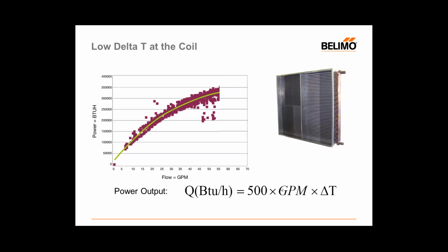This heat exchange process is governed by this formula, and most people in this industry are fairly comfortable or familiar with this formula, which is that the power output in BTUH is defined by 500 times the flow rate in GPM times the delta T in degrees Fahrenheit. So to really understand the exchange of BTUH to flow, we need to also examine how delta T plays into this. So we'll now plot delta T on this graph as well.